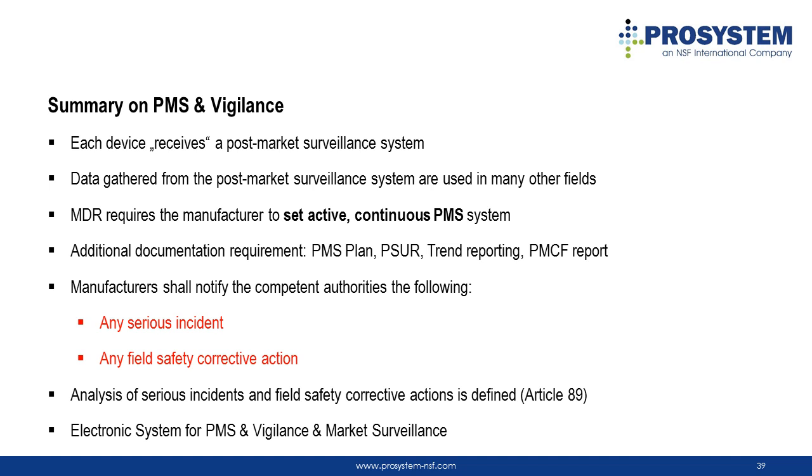There will be additional documentation requirements such as the PMS Plan, including the PMCF Plan, PSUR, trend reporting, and PMCF report. PMCF is part of PMS, aiming to confirm the clinical safety and performance within the product lifetime and to discover unknown risks or side effects.